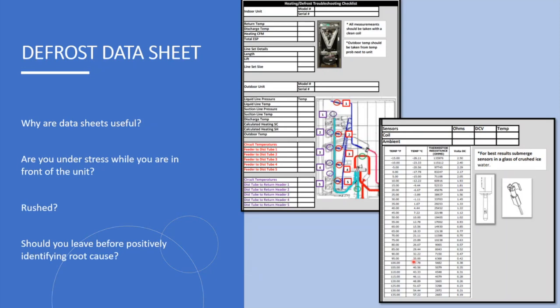We have a nice data sheet. If you reach out to anyone on the FSR team, we're more than happy to provide you with this. Because if you go to site and you leave before you've positively identified the issue, it's hard to troubleshoot later. So we do have this where it's got the model, serial number, return air temp, discharge temp, heating CFM, total external static pressure, some line set information, outdoor unit information, different line temperatures, subcool, superheat, outdoor temp, also individual temperatures of all of these tubes that we talked about on the coil, also your sensors, your ohms, your DC volts, and the temperature, and we even provide the chart.